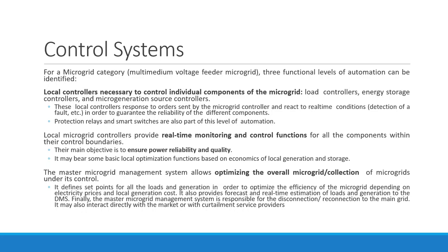If you are producing at lower cost than purchasing power at higher price, then generate your own generation. If you are capable of meeting the energy demand from your own generation, which is cheaper than the supply available from your Mahavitran company, then it is obvious to use this. If it is costlier, then purchase from there. If both are the same, then that's fine, you can go with either. Finally, the master microgrid management system will be responsible for the disconnection or reconnection to the main grid. So this is a master management. Okay, there are two microgrids operating under the master, so it will decide whether both should be disconnected or one should be disconnected, or what should be done, which should be reconnected. So that decision will be taken by the master management system.